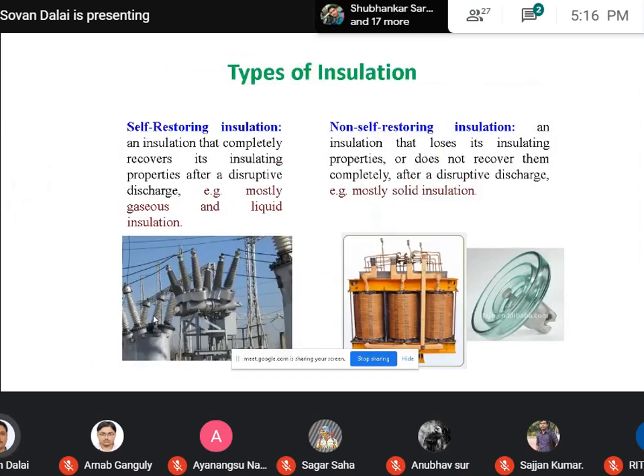So now we want to discuss transmission line insulation, and here I want to mention the types of insulation. According to the definitions, there are two types of insulation. One is self-restoring insulation, another is non-self-restoring insulation. Self-restoring insulation is what? After disruptive discharge, it regains its property, just like gaseous or liquid insulations. If you apply a certain voltage at which it breaks down, and then you remove that voltage, it will again return to its original position and again act as an insulation. That is basically called self-restoring insulation.